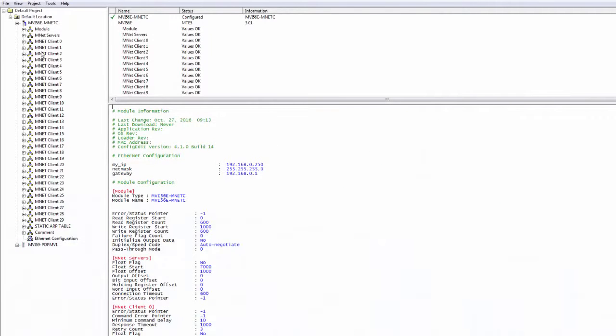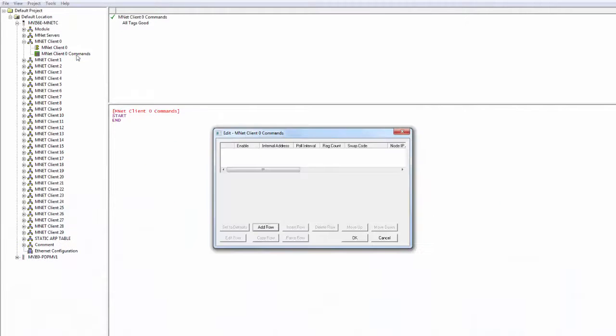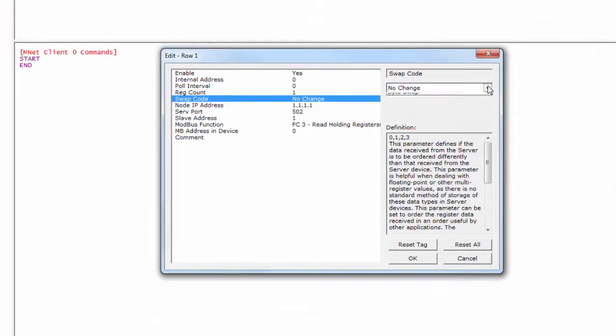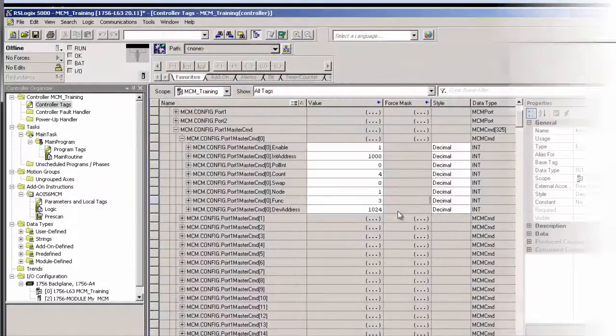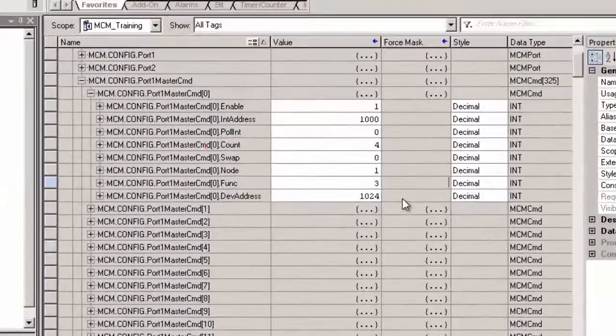In ProSoft Configuration Builder, when setting up your client commands, you can use the swap code function to swap words, bytes, or words and bytes. Or if you're using RSLogix 5000, when you set up the command simply enter one for swap.